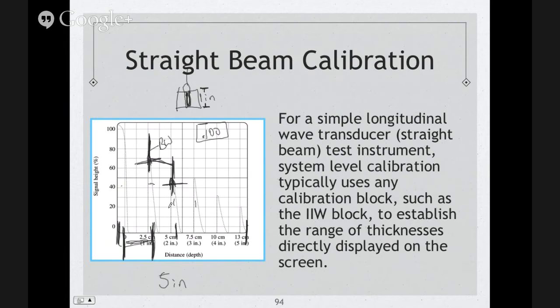So anyways, we're going two ways, right? We're going down and up, so we're dividing that distance by two. And that's why your echoes are always the same. Now, your initial is always going to be a little longer. It's going to take a little longer in time due to that cable. So you want to use your repetitions, and I use my alarms in my machine to get the distance from wherever my spike goes through to the other echo that's crossing my alarm.